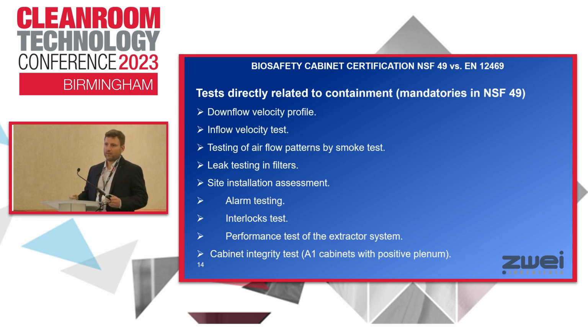It's a test where we need to elevate the pressure in the equipment and measure the decay of the pressure. It's very old and not usually used now.